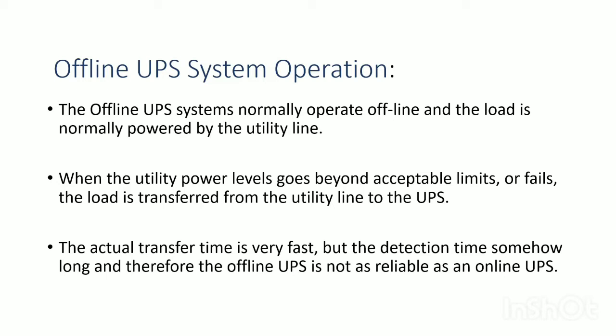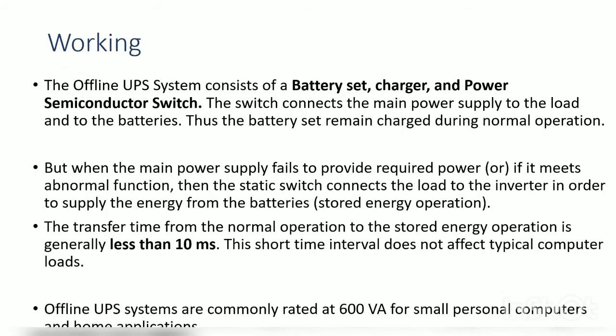In critical applications, offline UPS is generally not used — online UPS is more reliable. In hospital ICU applications, offline UPS is not suitable because there has to be a detection process to identify main supply failure before switching to UPS, which takes some time. For critical areas, only online UPS should be used.